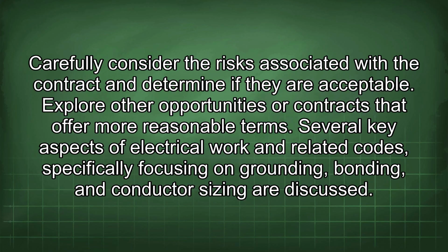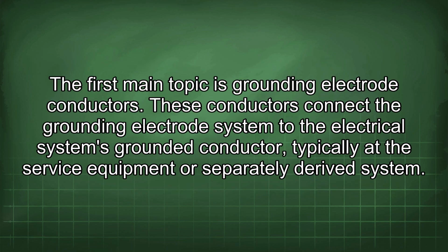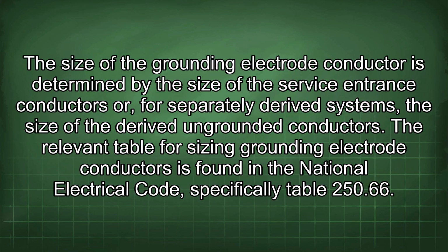Several key aspects of electrical work and related codes, specifically focusing on grounding, bonding, and conductor sizing, are discussed. The first main topic is grounding electrode conductors. These conductors connect the grounding electrode system to the electrical system's grounded conductor, typically at the service equipment or separately derived system. The size of the grounding electrode conductor is determined by the size of the service entrance conductors, or, for separately derived systems, the size of the derived ungrounded conductors.